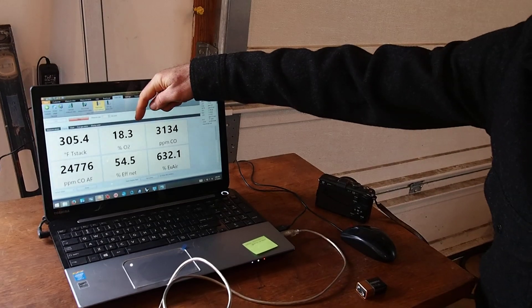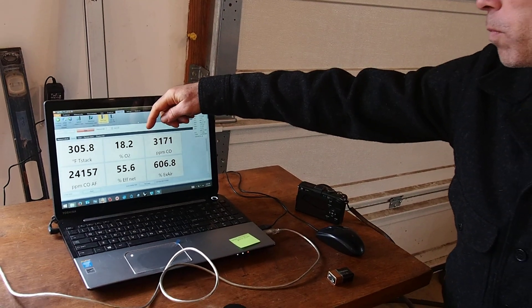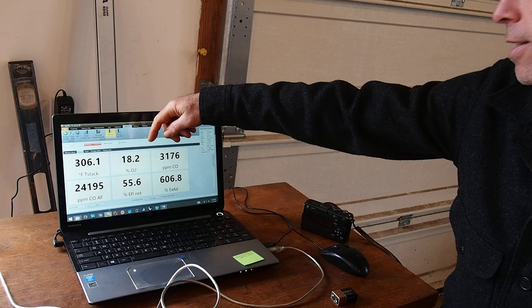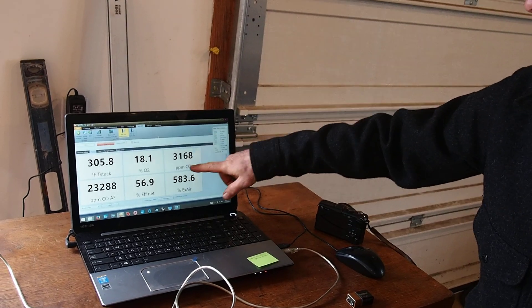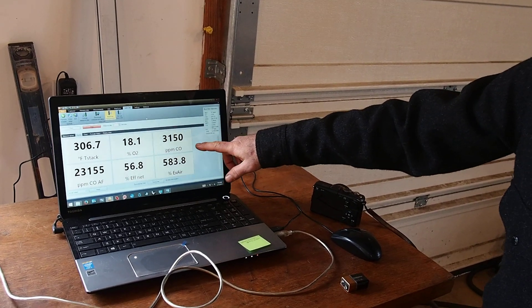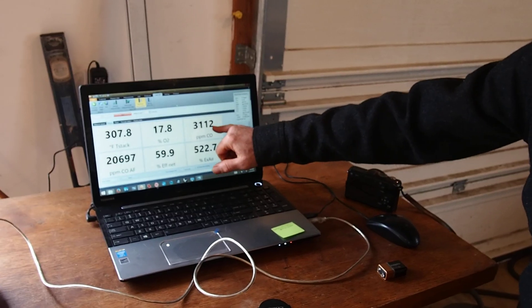Yeah, we'll see the oxygen starts to come down as the wood gas starts to pyrolyze and enter the burn chamber. This is the parts per million of carbon monoxide and that should spike right now, but we're dropping.